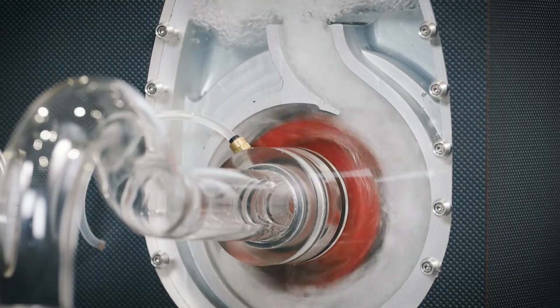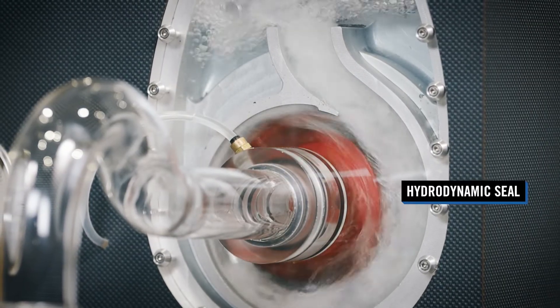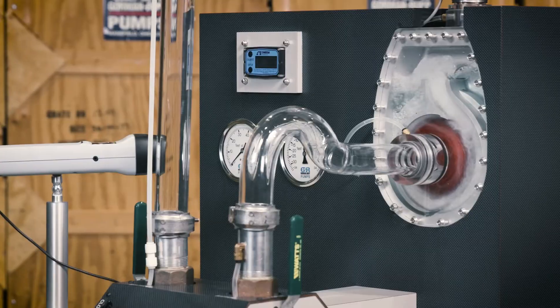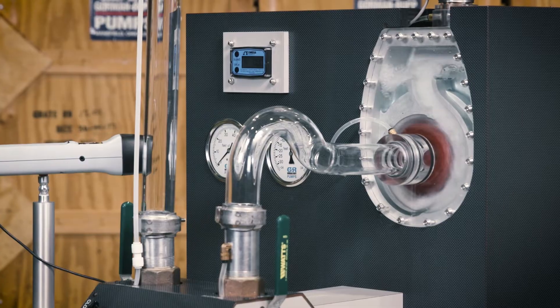During a priming cycle, the pump uses water to create a hydrodynamic seal between the impeller vanes and the wear plate. In this demonstration, the glass panel represents the wear plate.